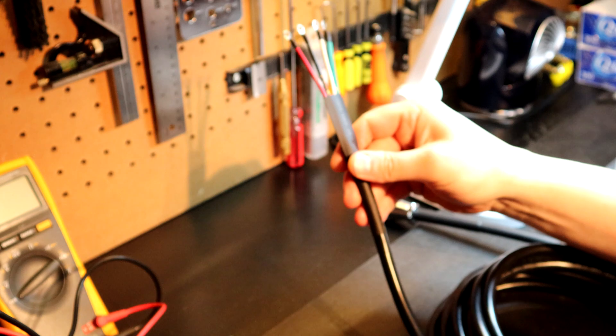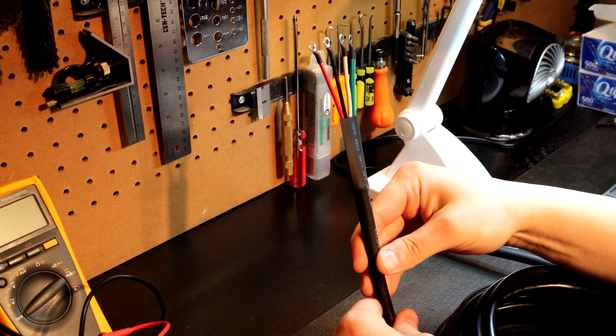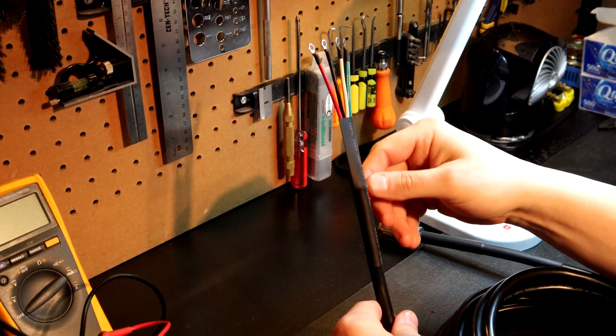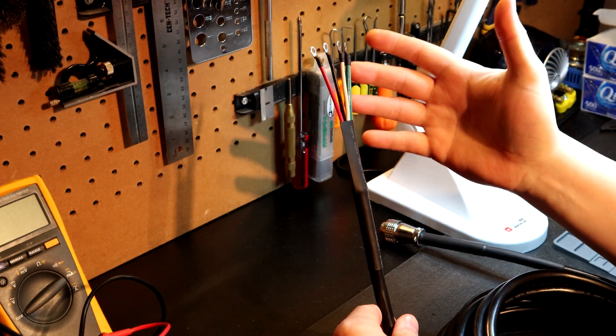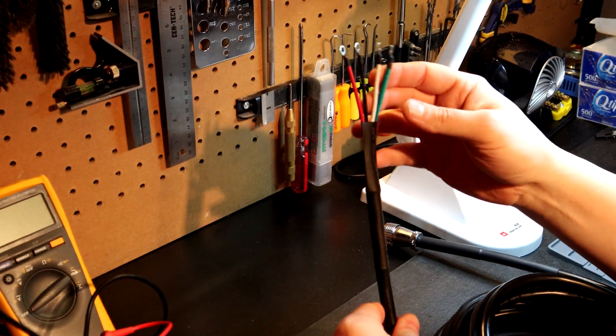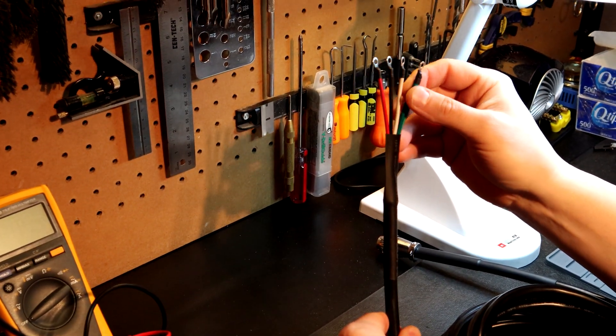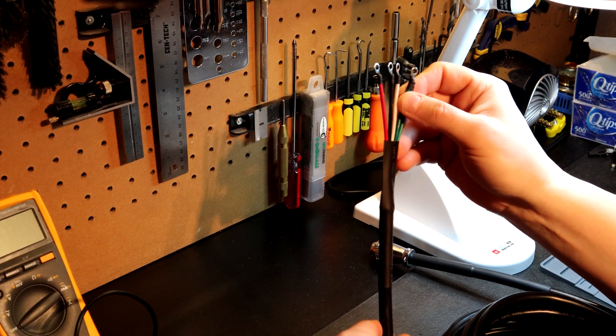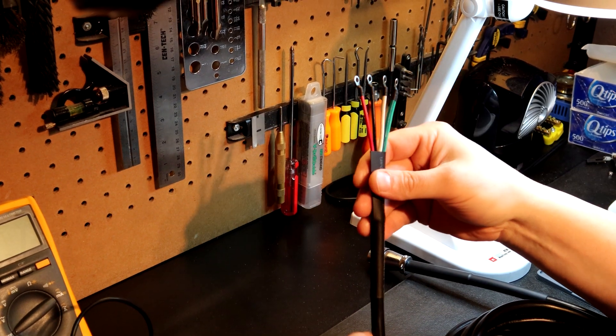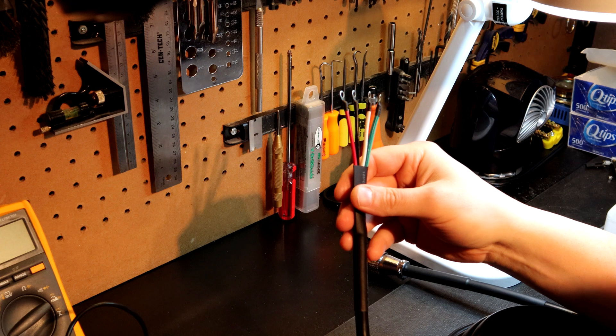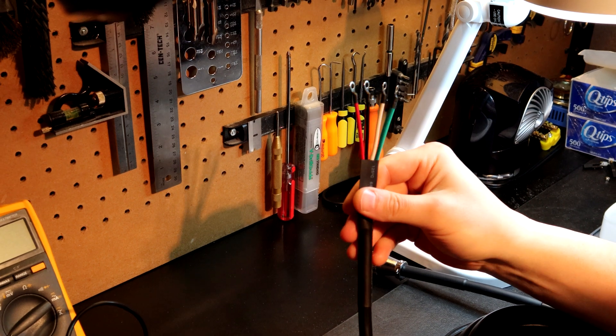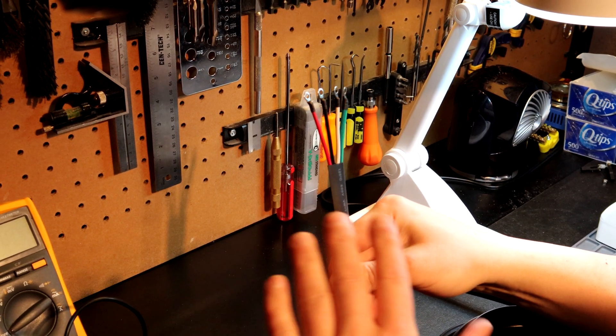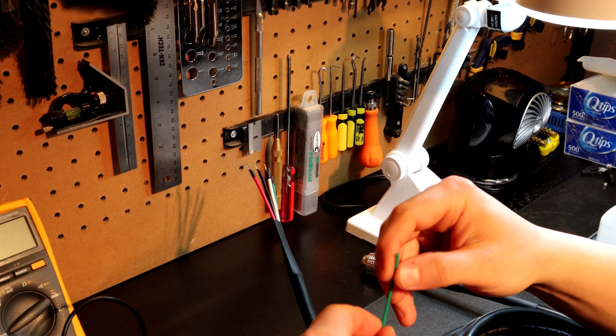I do have guys that will say they want to use the shield drain that's actually in the cable and use it directly to attach to the actual ground drain right on the actual spindle's connectors for the VFD and that's fine to do but what you'll typically find is that your flexibility on that actual lead is not nearly as good as silicone.